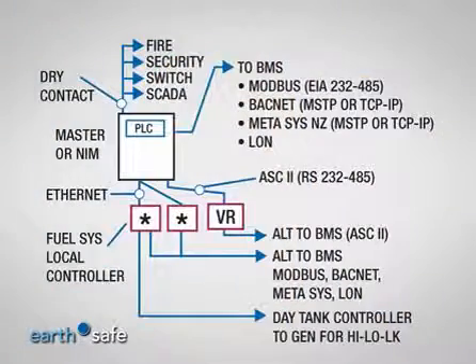There are a variety of building management system communication protocols. The fuel system controls need to communicate with the selected protocol for the building and the particular vendor for the system. The primary vendors of BMS systems are Siemens, Johnson Controls, Automated Logic, owned by United Technologies, Honeywell, who also owns Alerton, and TAC, who owns Andover. The primary communication protocols are Modbus, BACnet, Metasys N2, and LON. These may be either MSTP or Ethernet.